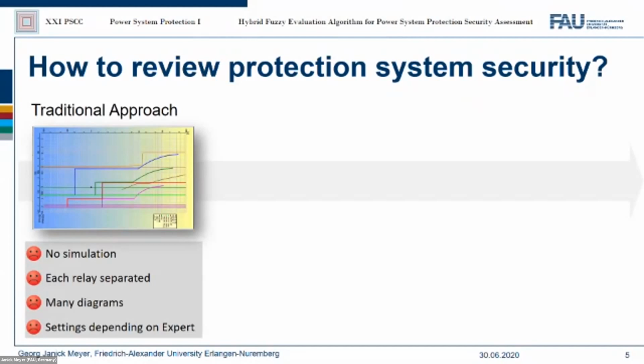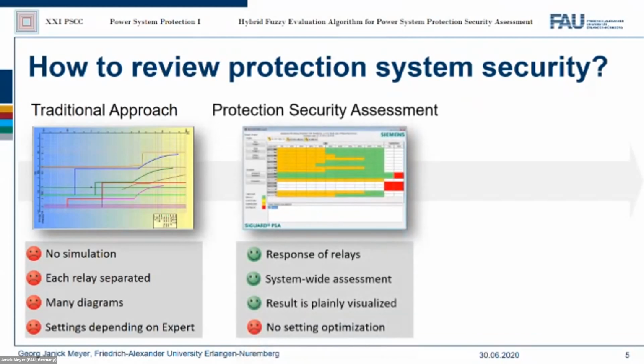That's why the Protection Security Assessment tool, short PSA, from Siemens has become known in recent years. It runs numerous short circuit simulations together with the protection system behavior to assess the response of all relays in a system-wide grid. At the end, the result is plainly visualized, as can be seen in the picture here in the middle, and weak points or bad relays can easily be found. Pretty much the only downside is that the system is not able to generate better settings on its own. For this task, an expert is also needed.